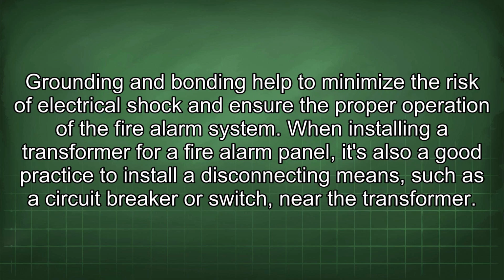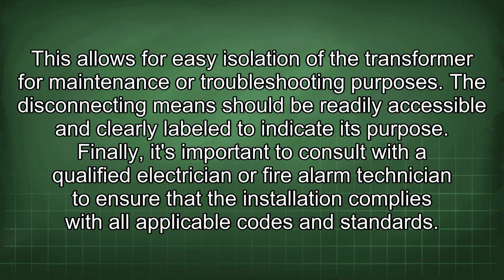Grounding and bonding help to minimize the risk of electrical shock and ensure the proper operation of the fire alarm system. When installing a transformer for a fire alarm panel, it's also a good practice to install a disconnecting means, such as a circuit breaker or switch, near the transformer. This allows for easy isolation of the transformer for maintenance or troubleshooting purposes. The disconnecting means should be readily accessible and clearly labeled to indicate its purpose.